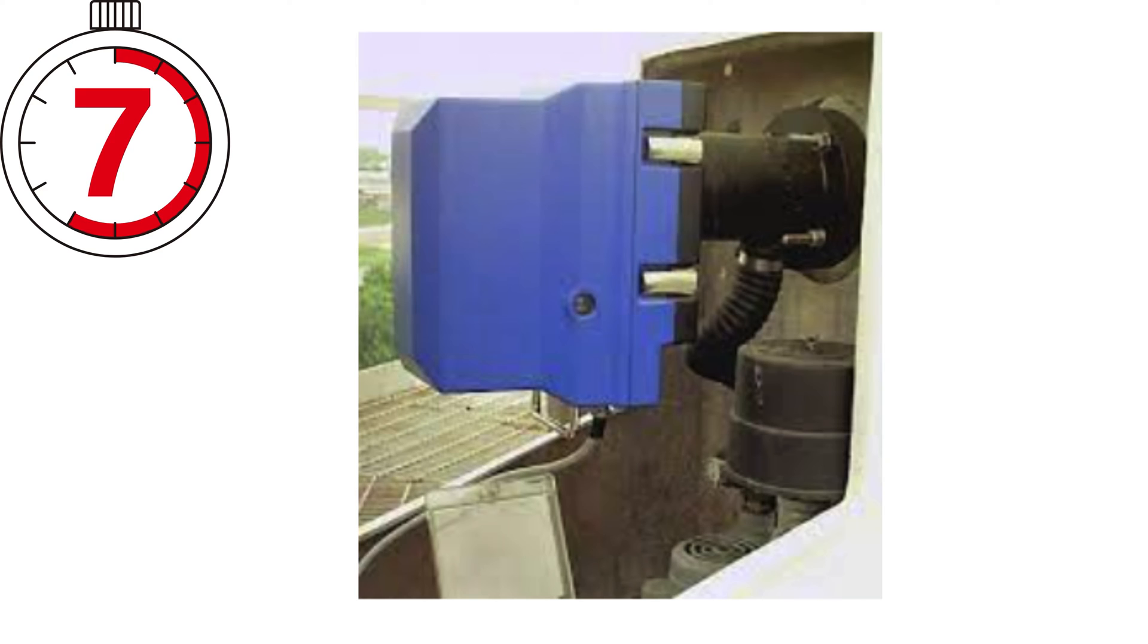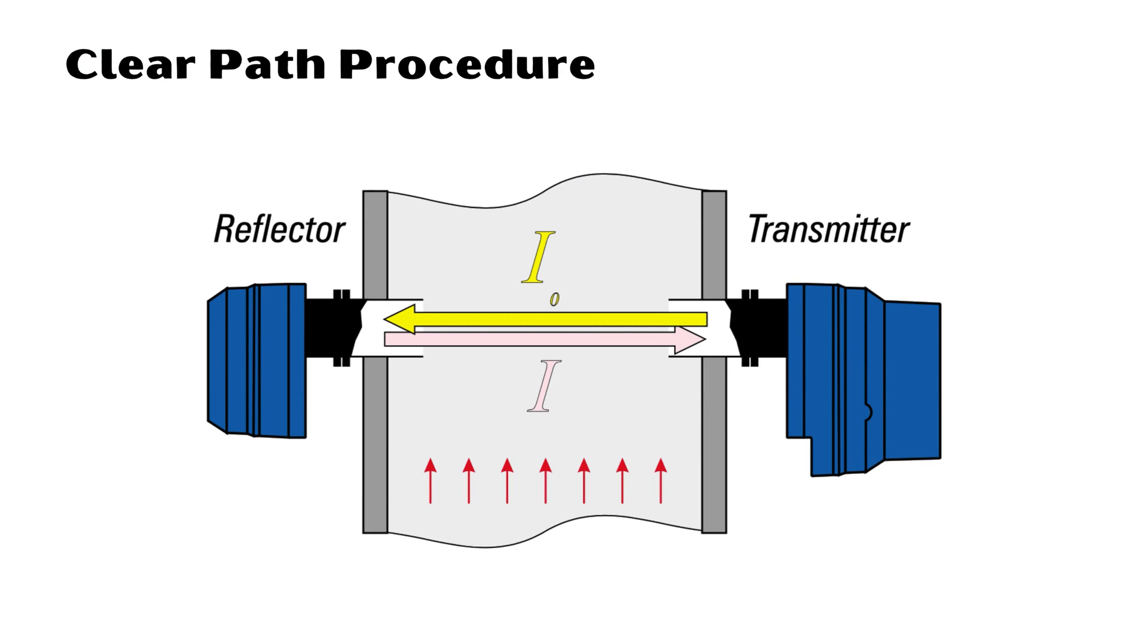Clear path procedure: In this procedure the measuring zero is set. The transceiver and reflector are mounted to the exact distance as on the stack or duct in a clean room with minimum dust in the air, such as an air-conditioned office. This procedure then adjusts the monitor so that a zero percent opacity reading is obtained. This procedure should be done in the factory and normally will not be done in the field.